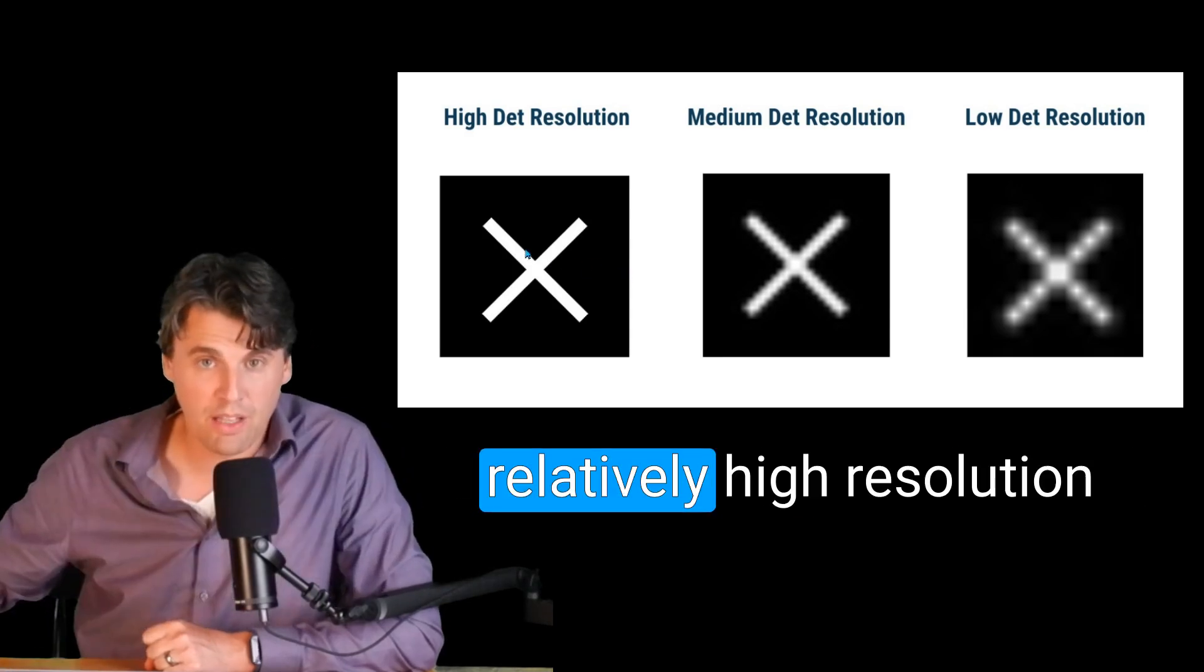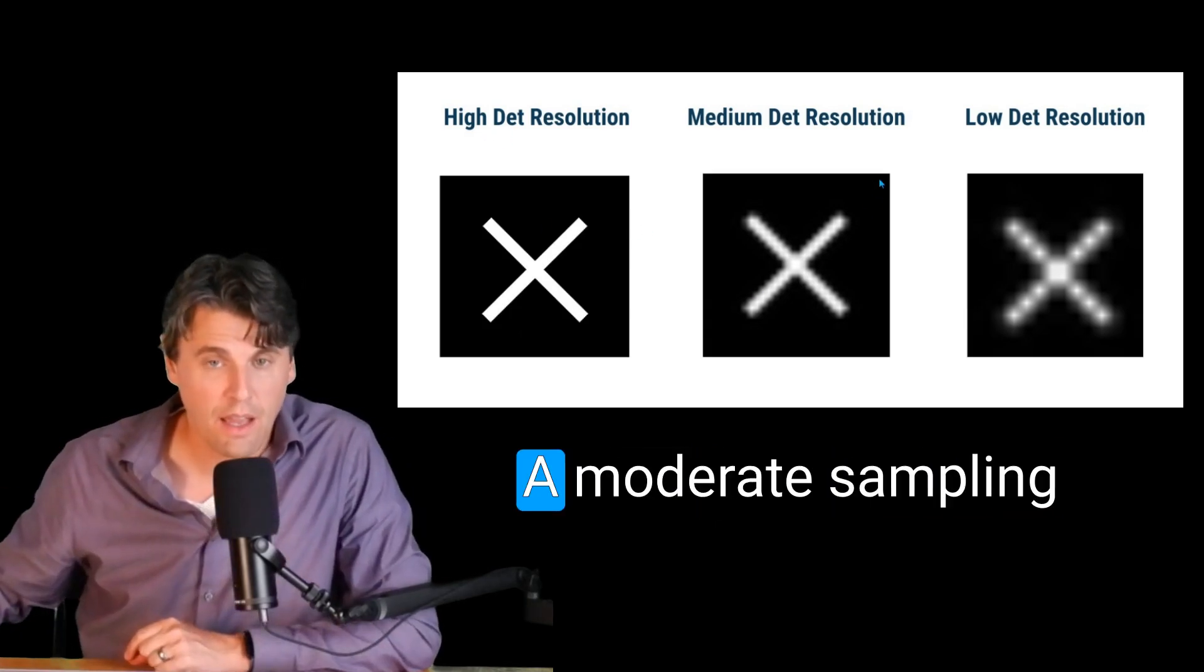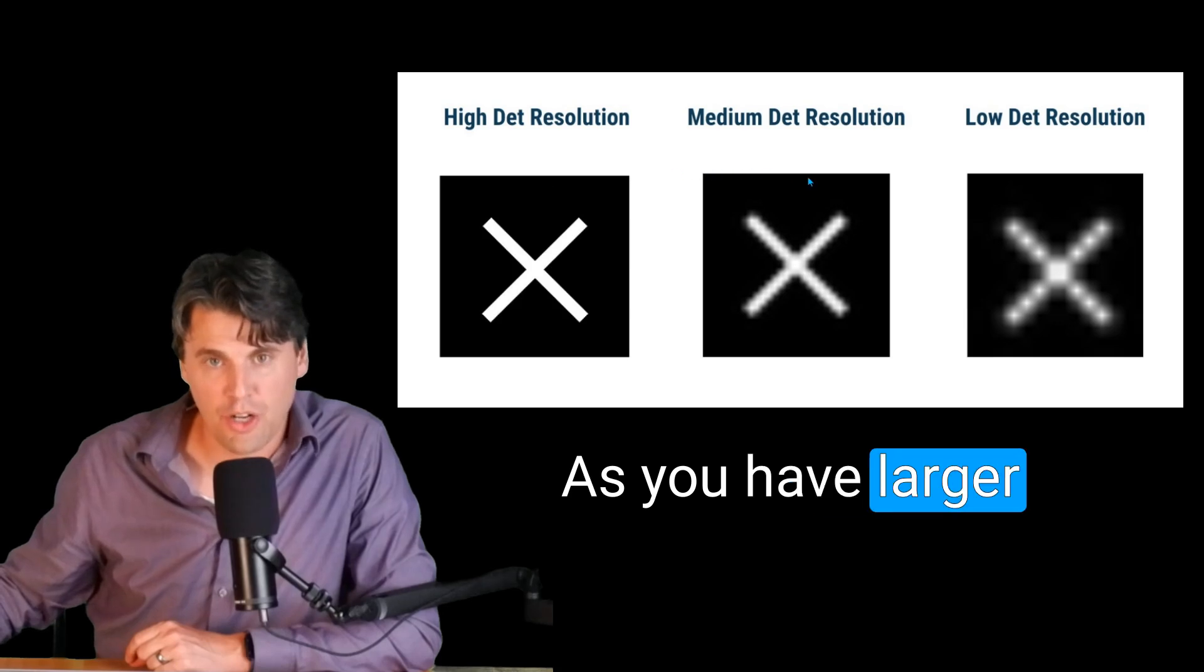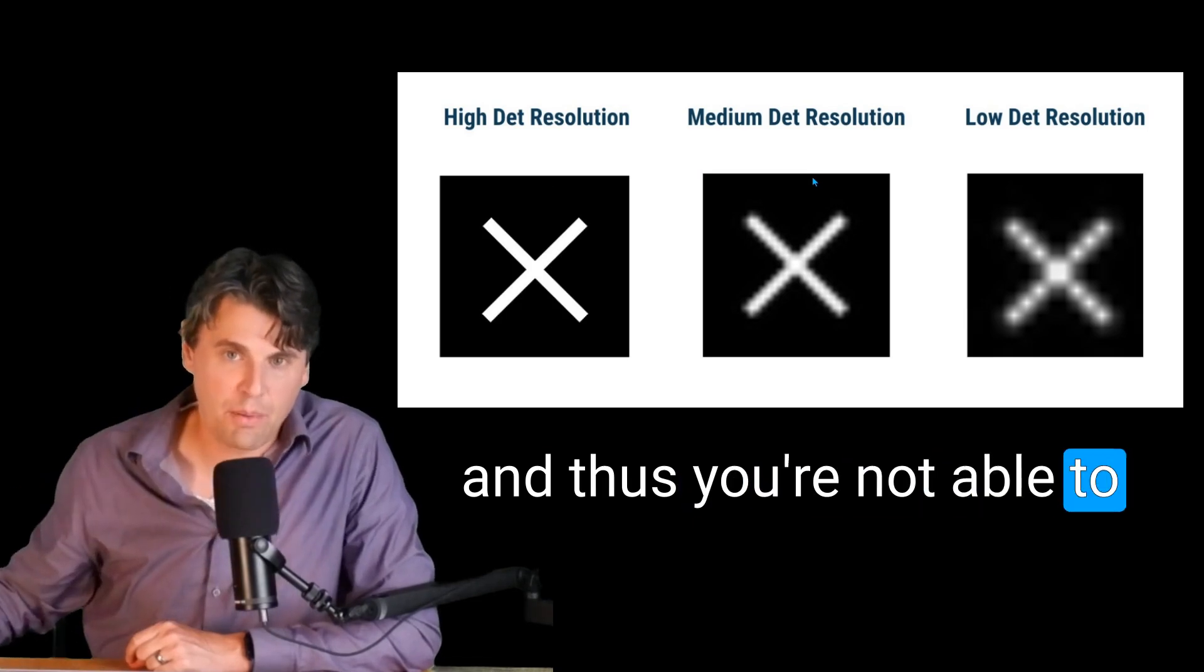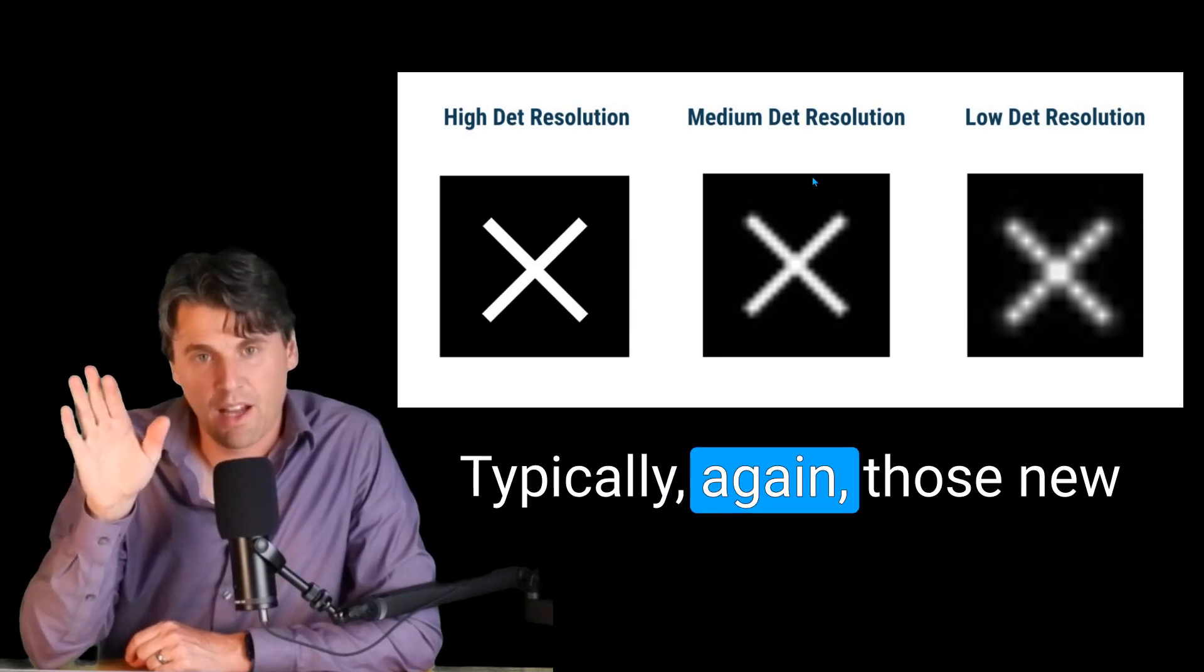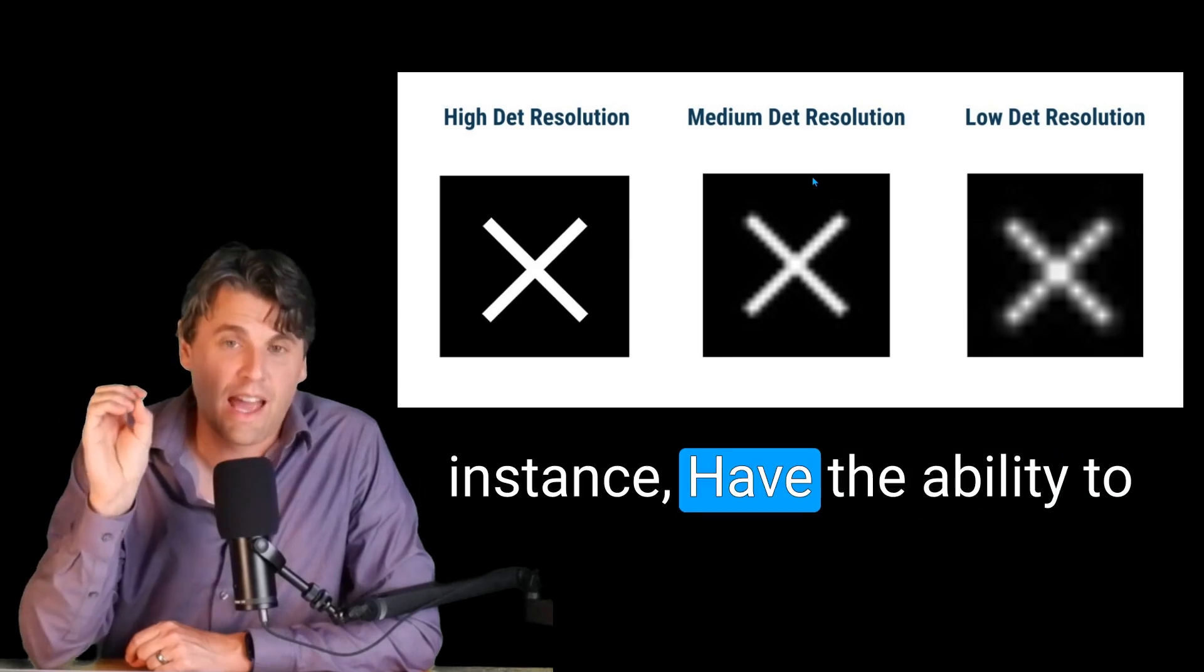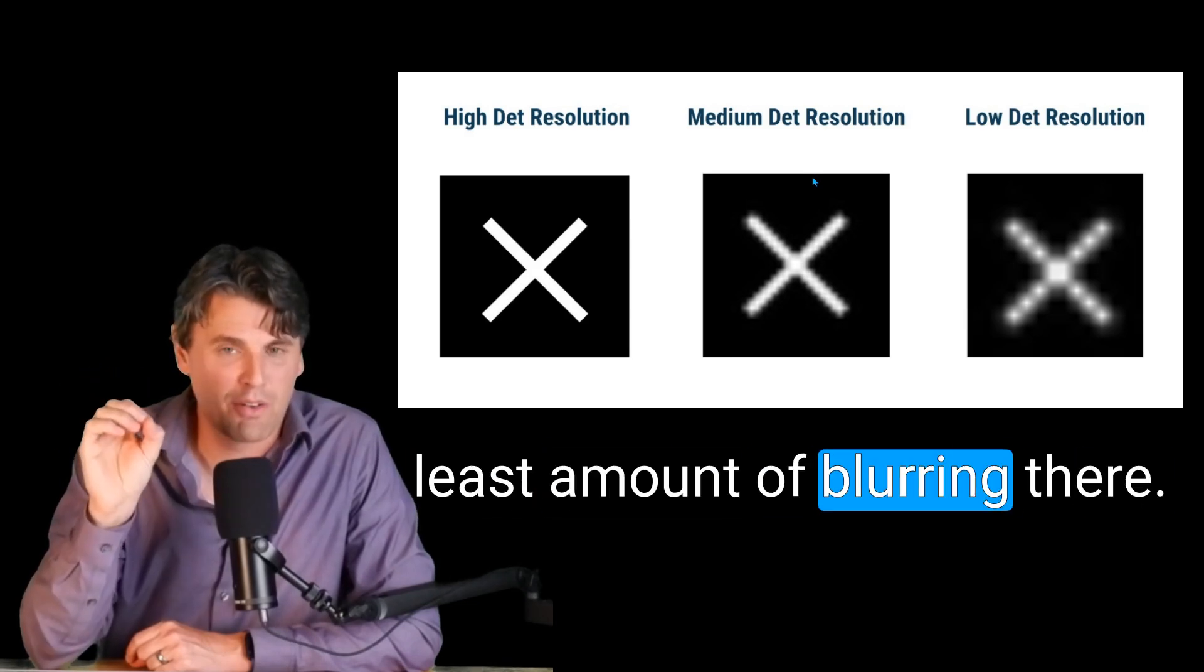Relatively high resolution images shown here, namely, well sampled on the detector side, a moderate sampling is shown here, and a lower sampling is shown here. As you have larger detector elements, you're decreasing the sampling, and thus you're not able to capture as high resolution structures in your image. Typically, those new direct flat panels that are made for mammography, for instance, have the ability to capture the highest space resolution, because there's the least amount of blurring there.